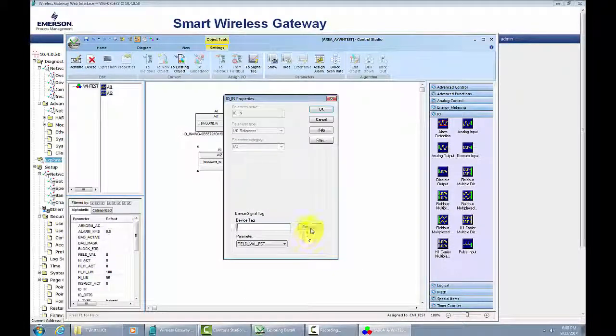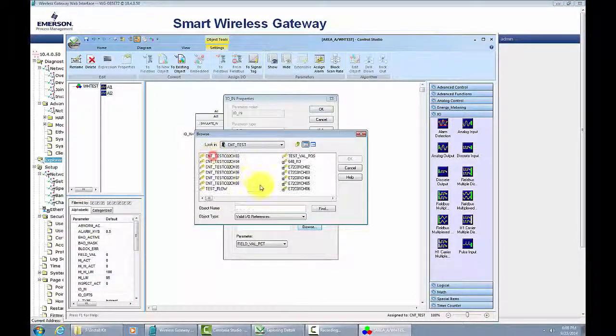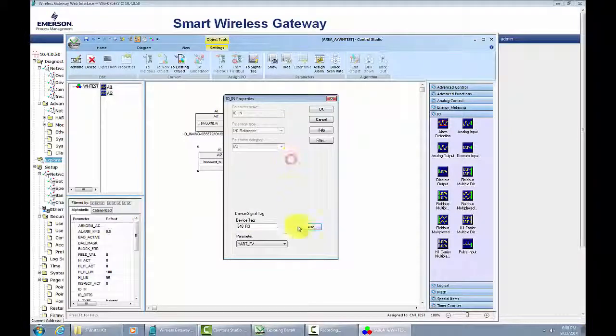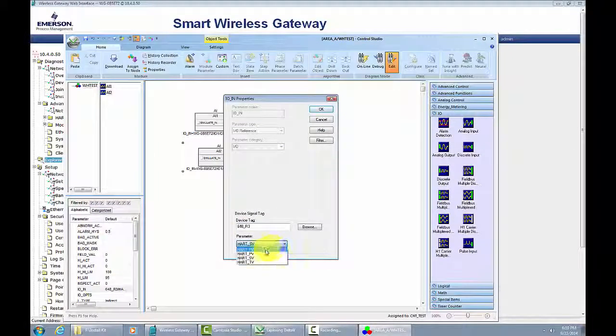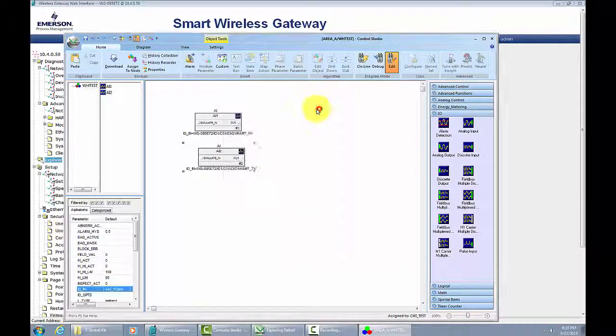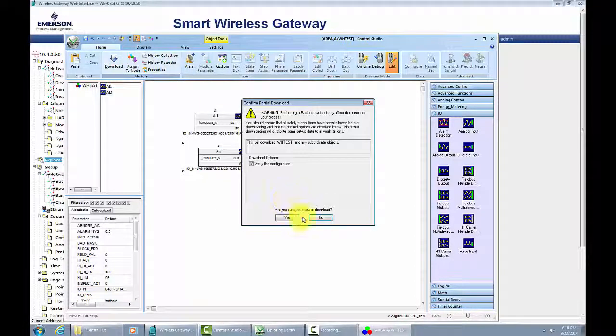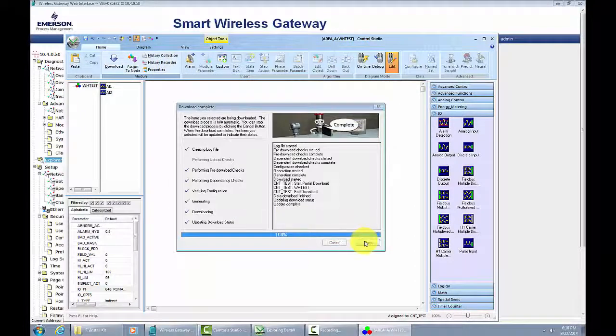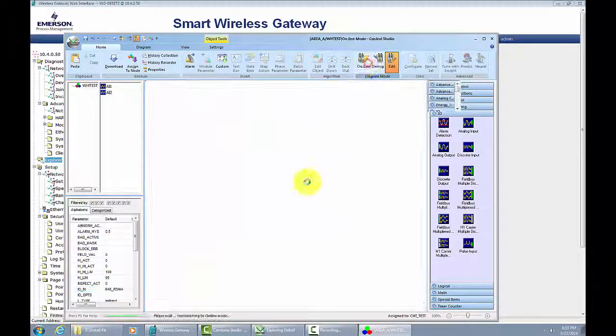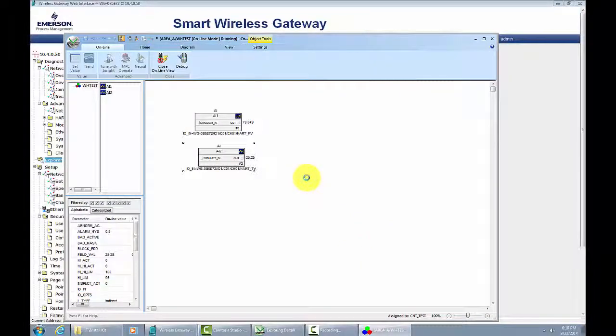The HART has up to 8 variables that can be communicated. The additional 4 are called additional variables. But in this case, we're just looking at the first 4. So we now have to download that into the DeltaV controller. So again, we download and we can go online and we'll see the values coming through. And right now we can see the PV and the TV.